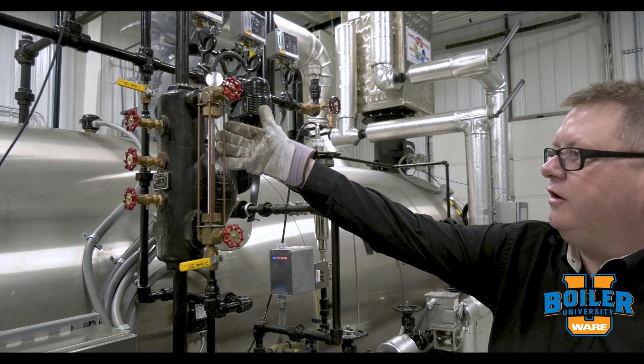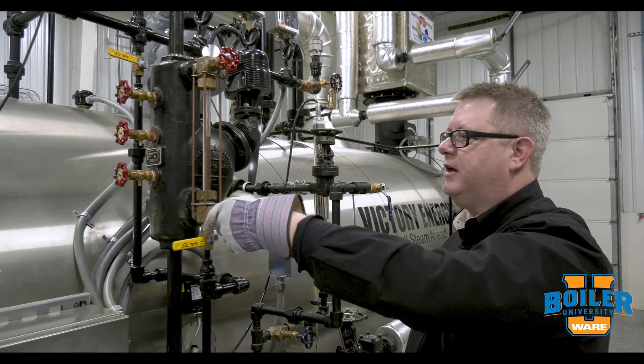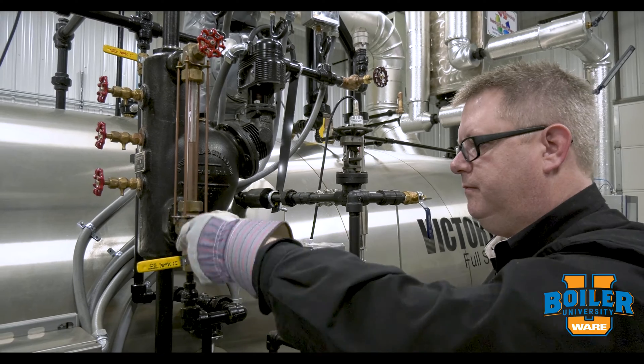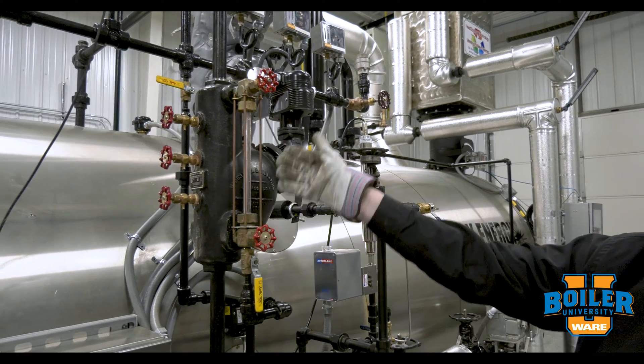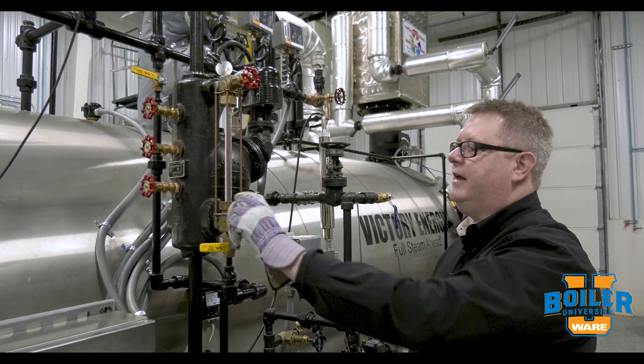If I want to focus on cleaning the inside of the sight glass, I can close the bottom connection. Then when I blow down, it's going to force steam through the top connection, which is going to give me a cleaning effect on the sight glass.